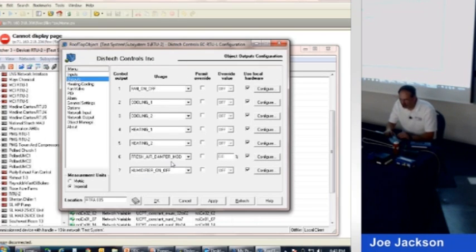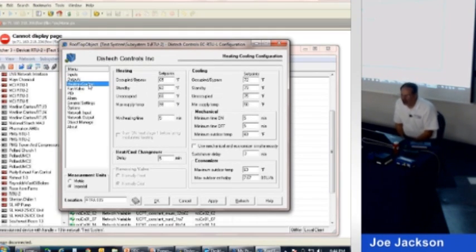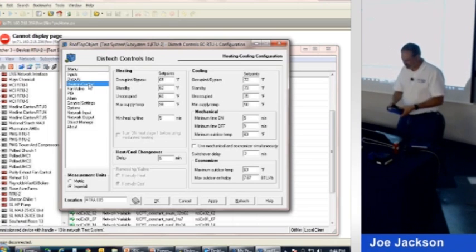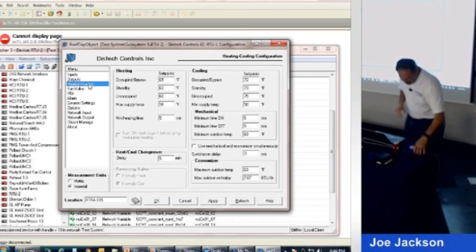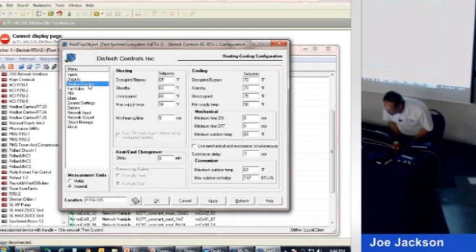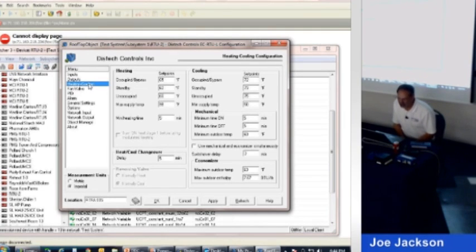So we got the inputs and the outputs. Let's look at this heating cooling thing real quick. Since we didn't pick a set point for our room sensor, we're going to have to change the set points from this. We're actually setting this up in what's called an LNS-based program. If you have one of these guys connected, you can actually do all of this through here without having to buy any real software. There's a little wizard thing you throw on your computer to do this, but it's all free and everything else. So you'll see what this thing generates here in a minute. It'll actually generate a picture for us to use to check the unit out.